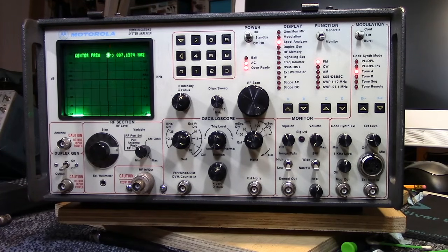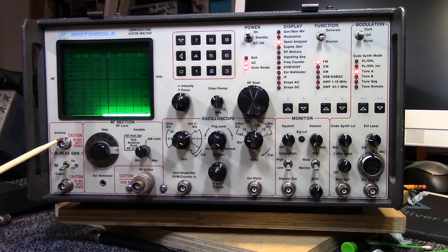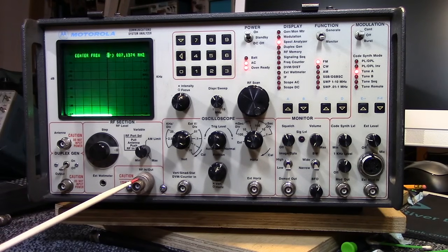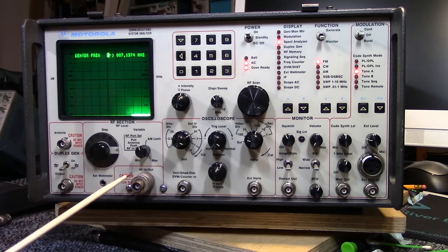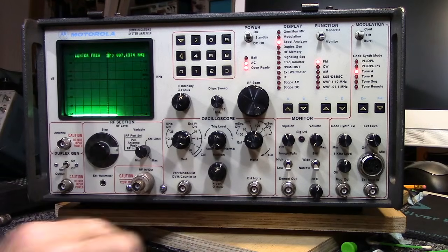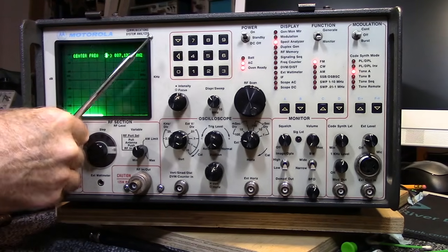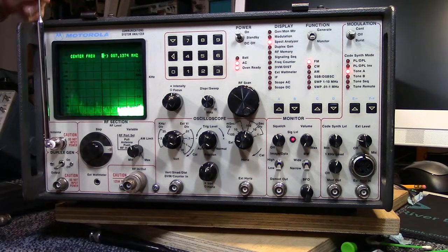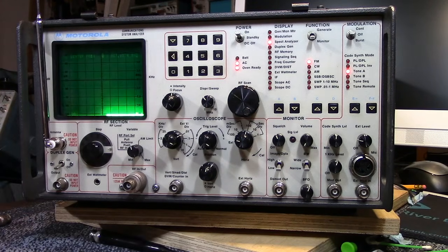Now here you got 2 inputs on this. You've got an antenna input. This is high sensitivity that you can measure off-air signals, and then you have this RF in-out connector here. This one has a dummy load that you can transmit in up to 125 watts. This is for a low-level input. This is for a high-level input. Anyway, for off-air tests, you can connect up an external antenna.